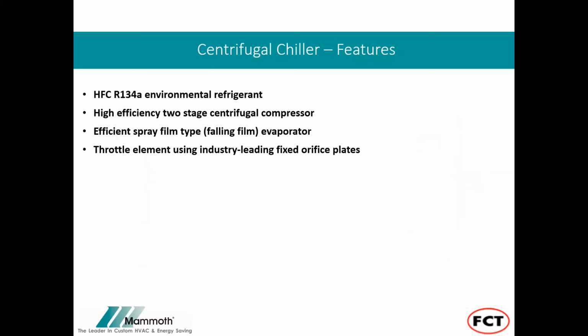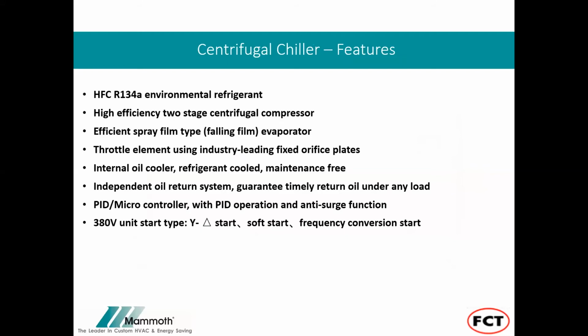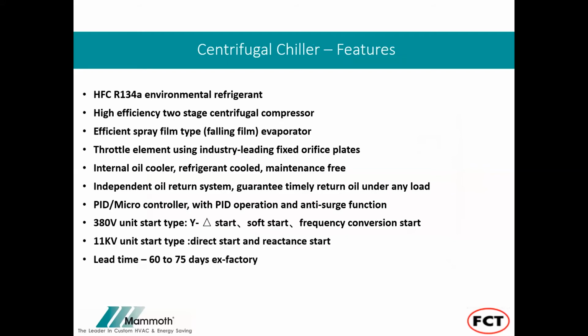Some of the main features of our chillers, I'm not going to go one by one, but you could see that. Some of the highlights are that we're using R134A, all the latest technologies in terms of the centrifugal chiller, and also the 11 kV power supply, we can also provide that. And the biggest advantage is that we can provide centrifugal chillers with a very short lead time of 60 to 75 days ex-factory China. So that's some of our features of our chillers.